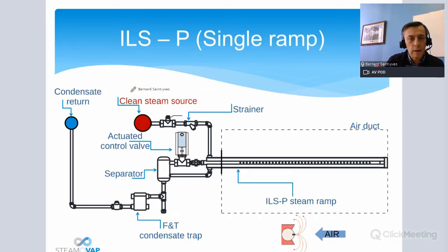Let's look again at the circuit. So the clean steam supply here, it is recommended to put a shut-off valve. Okay, why? Because when it's not the humidification season, you can close off the system. Otherwise, you will have constant heating up of the duct by the jacket. A strainer, this is to remove the dirt and any foreign element from the steam. It's called strainer, but it's a filter, and then it's going to, as I said, the jacket around, and then back here into the steam separator.